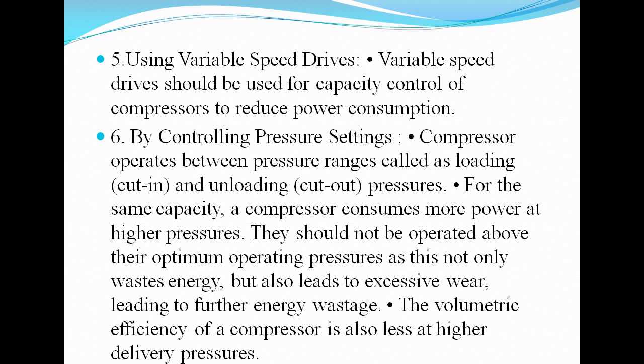Then using variable speed drives. Variable speed drives should be used for capacity control of the compressor to reduce power consumption. Variable speed drives mean the compressor will run at variable speeds as per our requirement. It will not run at one particular speed, so it will have steps.